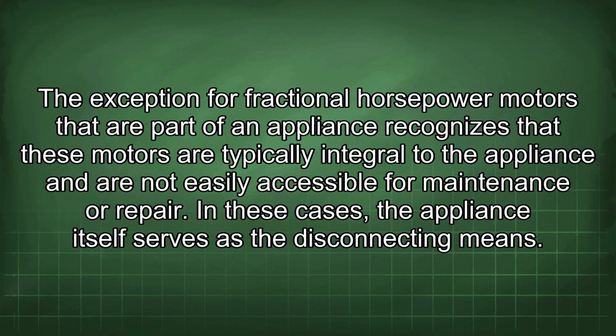The exception for fractional horsepower motors that are part of an appliance recognizes that these motors are typically integral to the appliance and are not easily accessible for maintenance or repair. In these cases, the appliance itself serves as the disconnecting means.